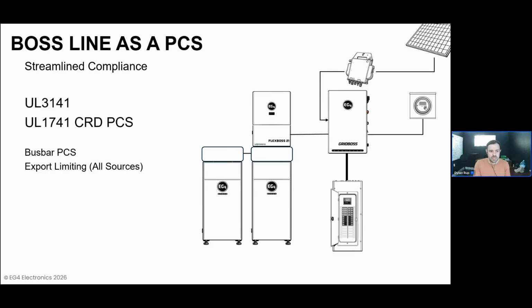The first is busbar PCS, which enables the system to limit the current delivered to the main bus of the system from all of the power sources. And it's more intelligent than simply derating the inverter, which is what you would historically see. What this does is it leverages a real-time consumption measurement from the various devices or power sources connected to the system, and can actually throttle both any AC-connected solar as well as the EG4 energy storage system connected, to ensure that the mix of all the different power sources never exceeds 80% of the busbar rating of the system connected to the device.